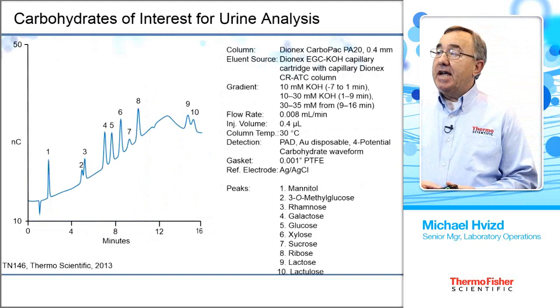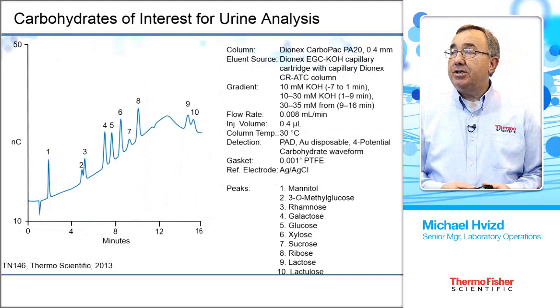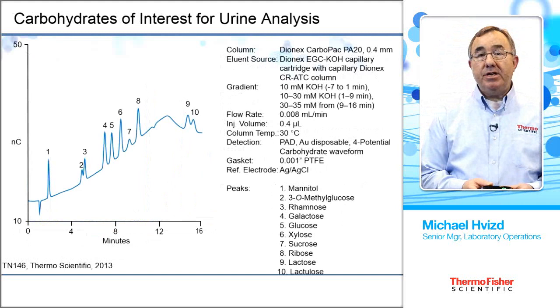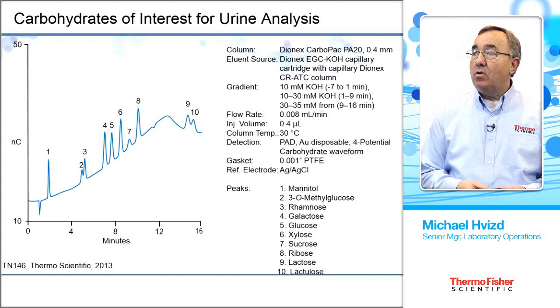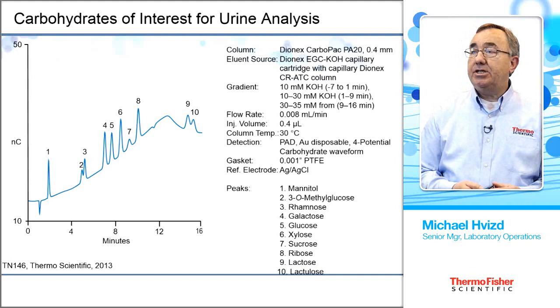Here's an example of a biological application — looking for carbohydrates in urine. This separation is done with a hydroxide gradient using the eluent generator module, running at about 8 microliters per minute in capillary format. The separation shows a change in the baseline due to the change in hydroxide concentration, going from 10 millimolar up to 35 millimolar KOH. Even with that baseline shift, we're still able to resolve all peaks of interest and get good detection from all of them.